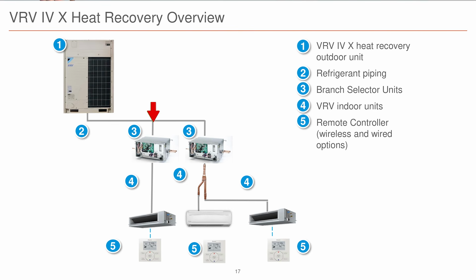We've got a 1-to-1 configuration on that first fan coil, where it's just one branch selector box to one fan coil. That fan coil can do whatever the heck it wants to. It can heat, it can cool, it can run in fan mode. But then you'll notice that I have one branch selector box connected to 2 fan coils. Well, now these 2 fan coils are coupled together. They're married together. They have to make decisions together. They can't just do one thing and the other one does the other. They're both tied to one box that's going to determine whether it's heating or cooling.